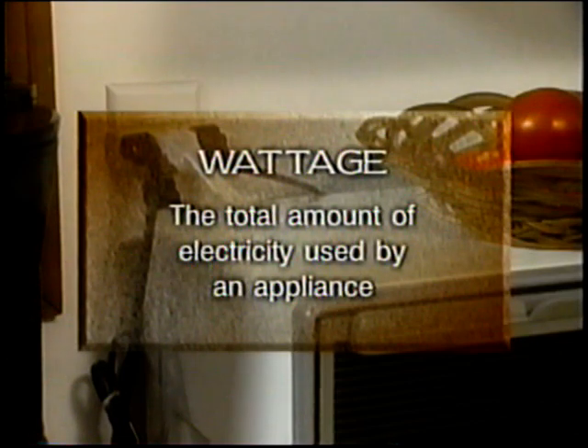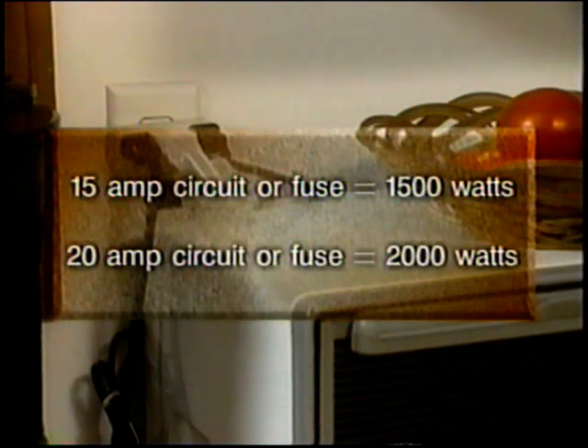Of course, it's reassuring to know that fuses and circuit breakers can help protect circuits against overloading, but the best solution is not to overload the circuit to begin with. A 110 or 120 volt circuit can only handle a specified combined wattage of all the electrical devices connected to it. For example, a 15 amp circuit can safely carry 1500 watts. A 20 amp circuit can handle 2000 watts.